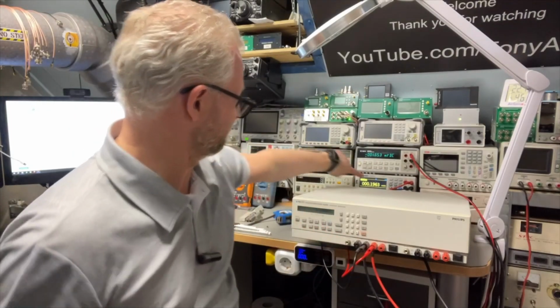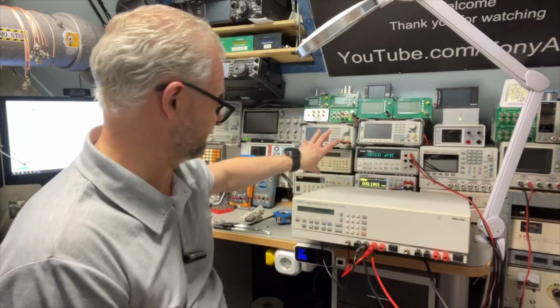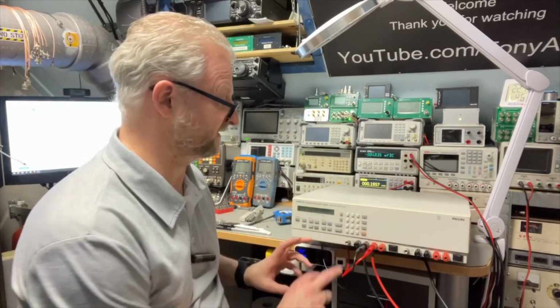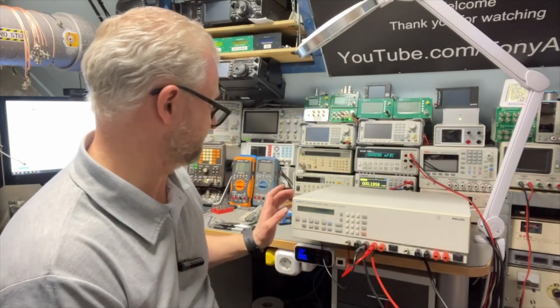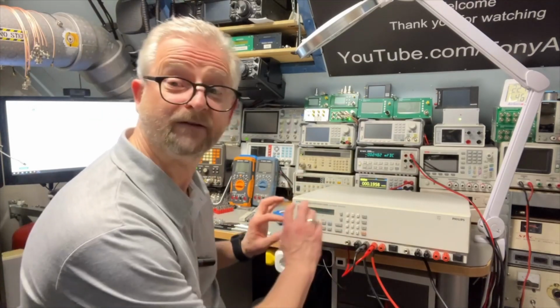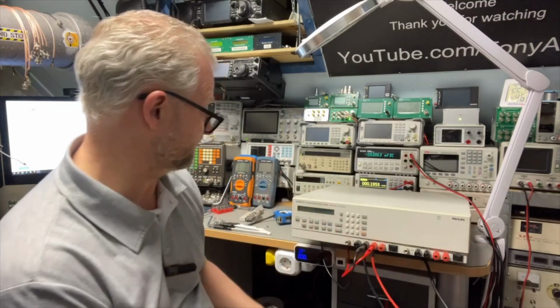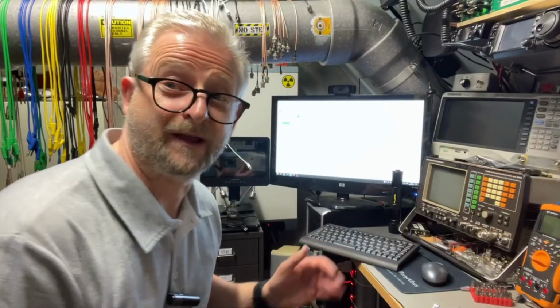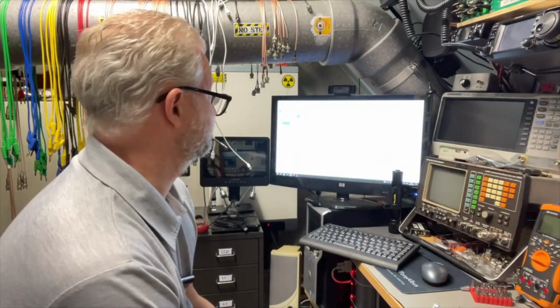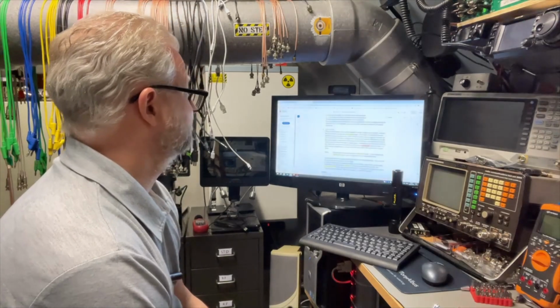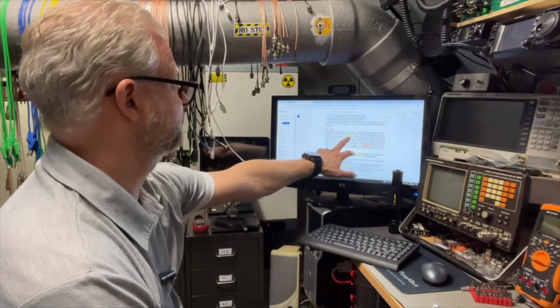We have a few dots behind the 0, but that's probably something we can calibrate since it's a programmable power supply. So if we have the correct code, we should be able to do that. For the calibration, I need the calibration code, and I see as an example they use here the...